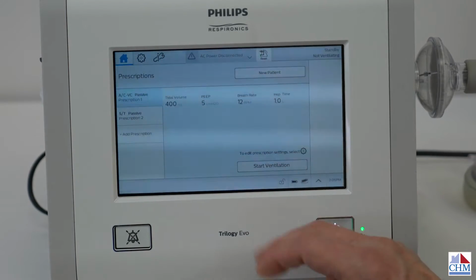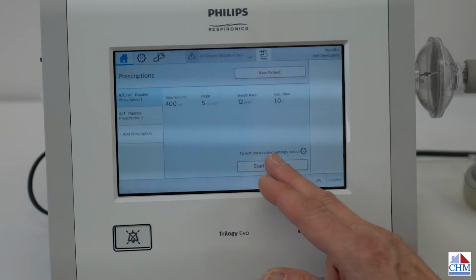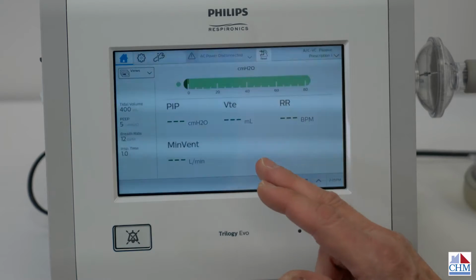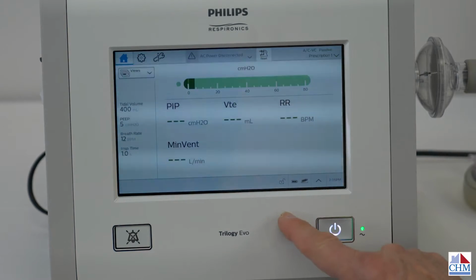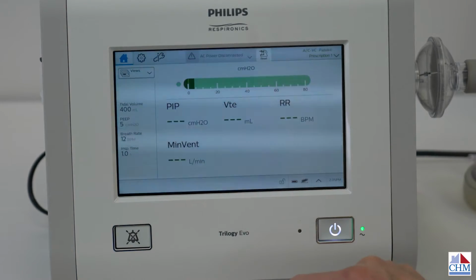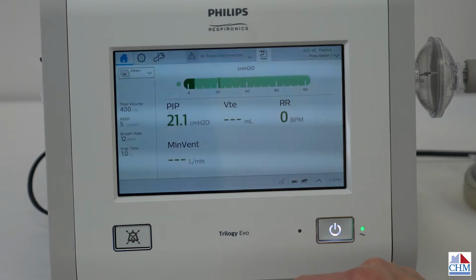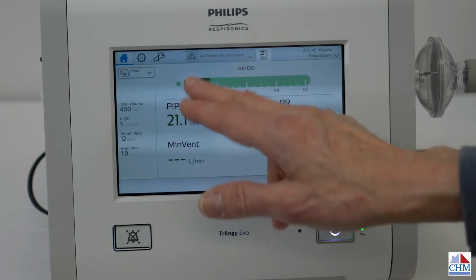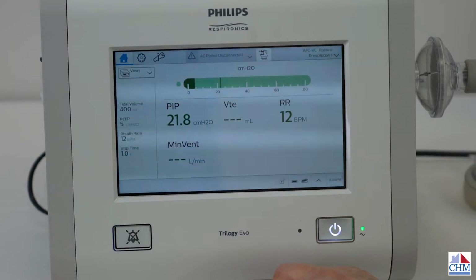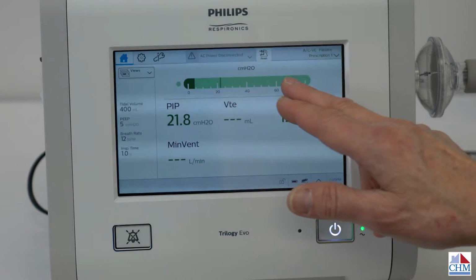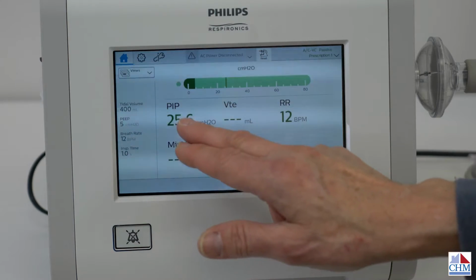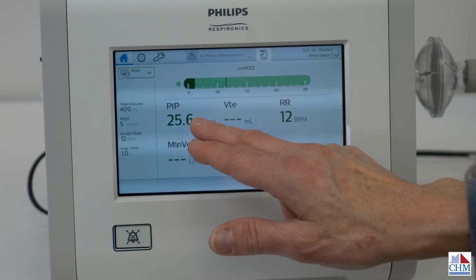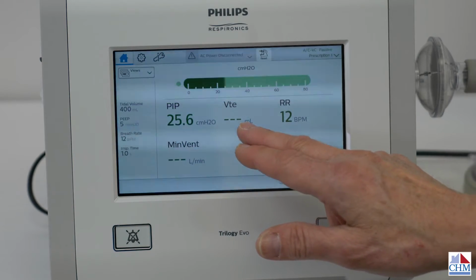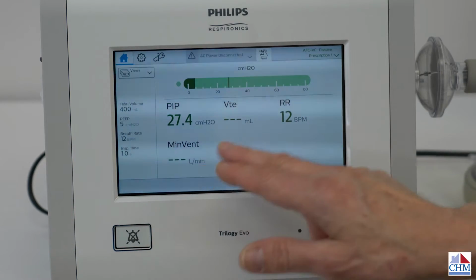And this is a touchscreen. So if I want to start ventilation, I can actually touch that. And instead of having the buttons down here like on the Trilogy, we could actually touch the screen to go ahead and start ventilation. Once ventilation is begun, you can see that I've got the display here showing the pressure bar. It is showing the peak inspiratory pressure. The VTE will come up here in a little bit after it picks up an average.